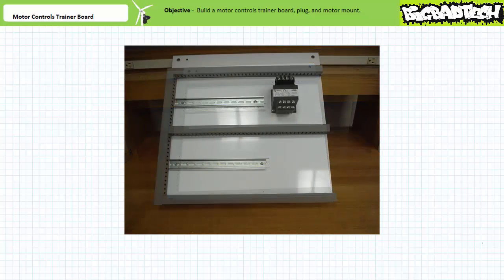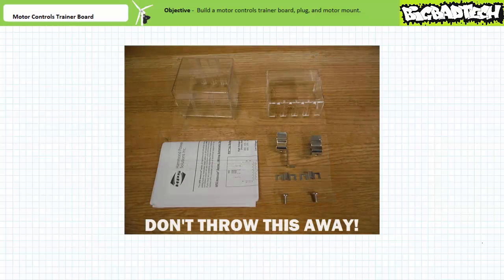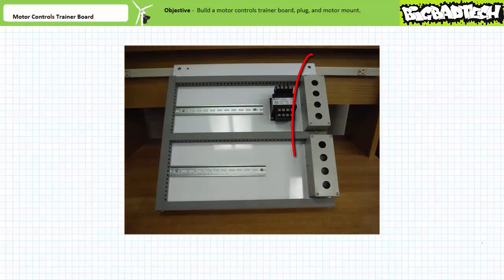If everything you plan on making use of is DIN rail mounted, by all means, use longer lengths of DIN rails. Next, mount the control transformer to the right of the top DIN rail. We'll wire up the control transformer, test it, and make use of it in later lectures. Keep the associated datasheet, wiring diagram, voltage links, fuse holders, and finger safe covers in a safe place until then. Finally, mount the push button enclosures on the far right side. We'll fill these enclosures with input and indicator devices in later lectures.